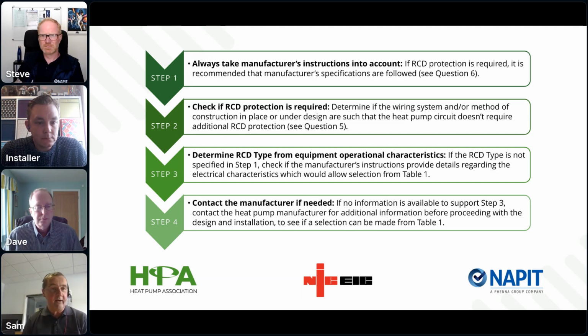I can think off the top of my head of an example of another piece of equipment which still talks about protect with a fuse. Now, there's no need for it to be protected with a fuse because there are better types of protective devices now. So sometimes the regulations have leapfrogged manufacturer's instructions, and sometimes manufacturer's instructions have leapfrogged the regulations because they're both cyclic and they're not actually totally in sync. So that's why it's a generic statement: take account of manufacturer's instructions, but it's still down to the designer of the electrical installation to follow and comply with 7671 for the electrical installation aspect.